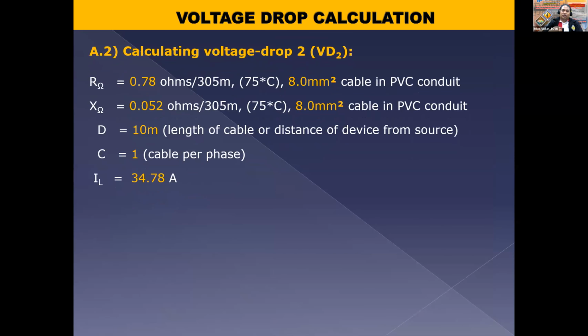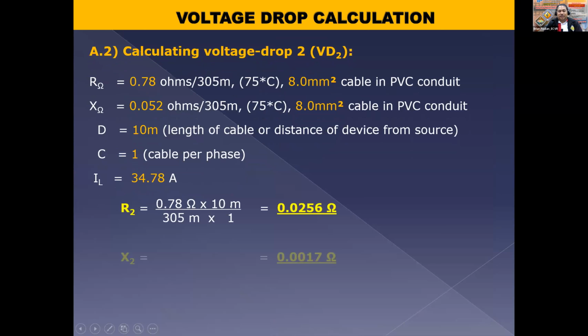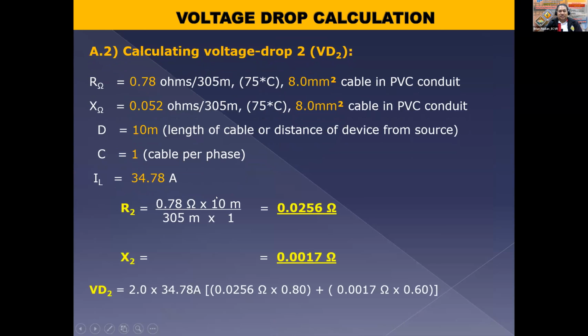Then, for the voltage drop from the main bus to the load na talaga, ito yung kuha natin. So, ang kable natin is maliit na, 8 mm squared, no? So, same process, convert to the actual length at 10 meters, yung reactances and resistances natin. So, voltage drop natin is 1.49 volts, no? So, now, solving for the percent voltage drop.